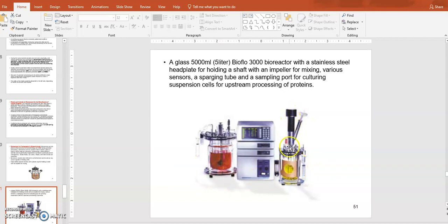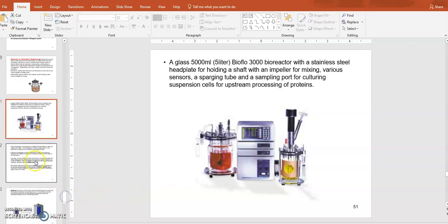And then all those spinners, with the controller, will keep the cells spinning and suspended, and air will be pumped in. So an air filter is in there, and other probes will be embedded there, like a DO probe, dissolved oxygen probe, or pH probe, and a thermometer, all those things. They are hooked up with this control tower, so it does real-time reading all the time. If, for example, pH is dropping too fast, it's going to give you an alarm so you can do something about it. If the dissolved oxygen level is going down, it's also going to give you an alarm, or it's going to kick in automatically to pump more oxygen in. So it can control those. That's what the bioreactor designs would allow you to do.